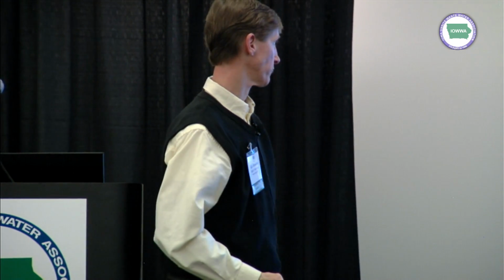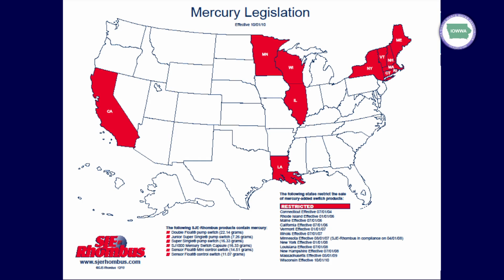Just because, again, with mechanical contacts, there are more problems that can occur on those contact points that you don't typically see with a mercury switch. So as long as they're legal, that would be the route I would steer you. For every mechanical switch, we have an equivalent mercury switch available too. All right, there are states across the country that have outlawed mercury. There are 12 states in the U.S. It wouldn't shock me if in the next 10 years you see a whole lot more red on the map.